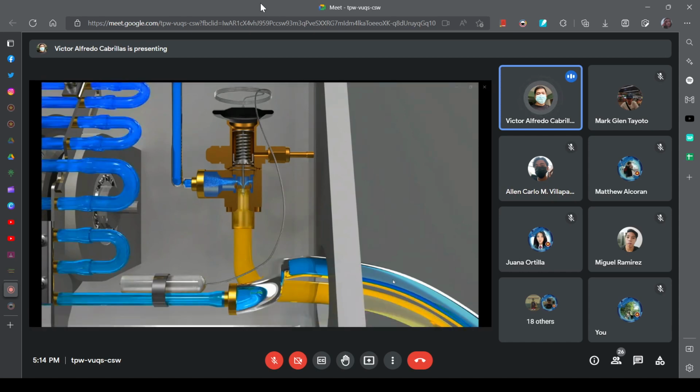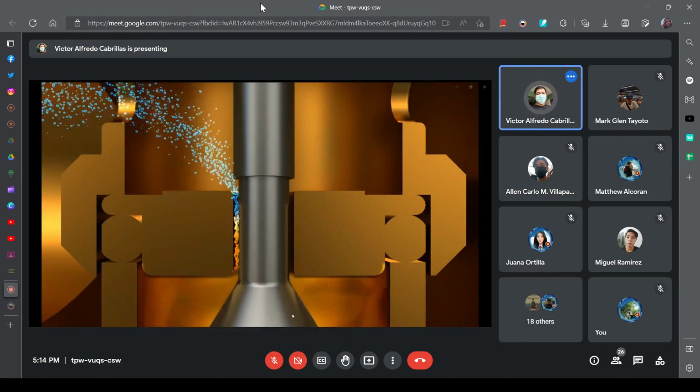A sensing bulb is installed on the exit of an evaporator and detects temperature. Inside the storage is fluid sensitive to temperature changes, and as the temperature at the exit of an evaporator rises, the gas pressure rises, which in turn presses on a spring to send more refrigerant to the evaporator. When the amount of refrigerant going into the evaporator surges, cooling emission surges too.